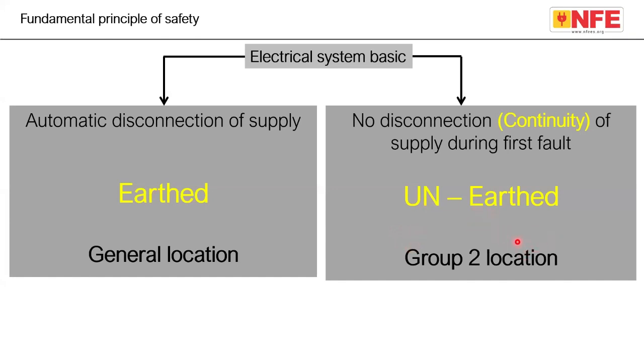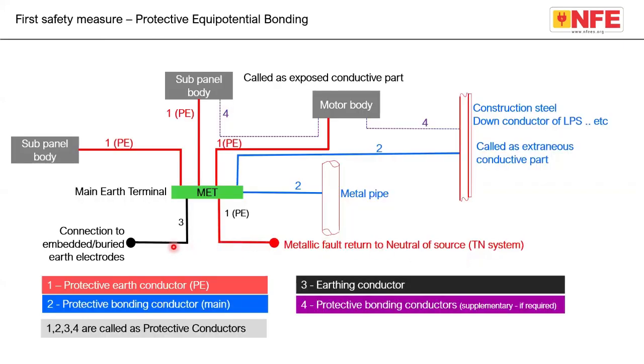Similarly, for group 2 location, an unearthed system is used, because continuity of supply is necessary. What is missing in almost all our electrical installations is a measure called protective equipotential bonding. What you are seeing in the picture, for example, sub-panel, motor body, some kind of metallic parts, metal pipe, all these things must be interconnected to a common bus bar. And this is called earthing, unfortunately very rarely seen in our nation. And that is the reason for shock and fire hazards.